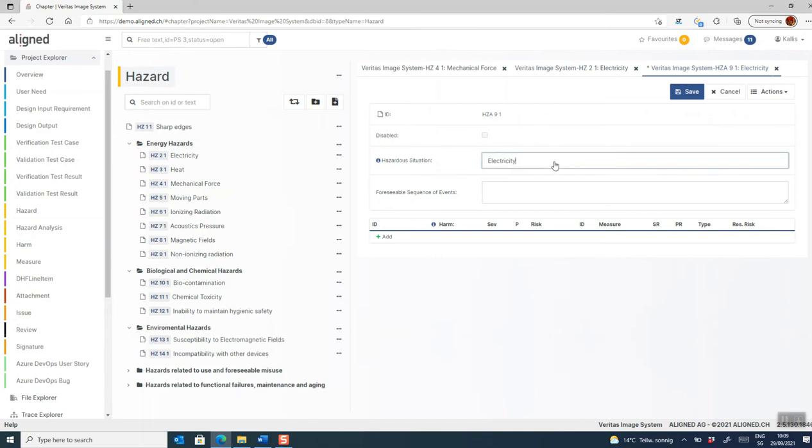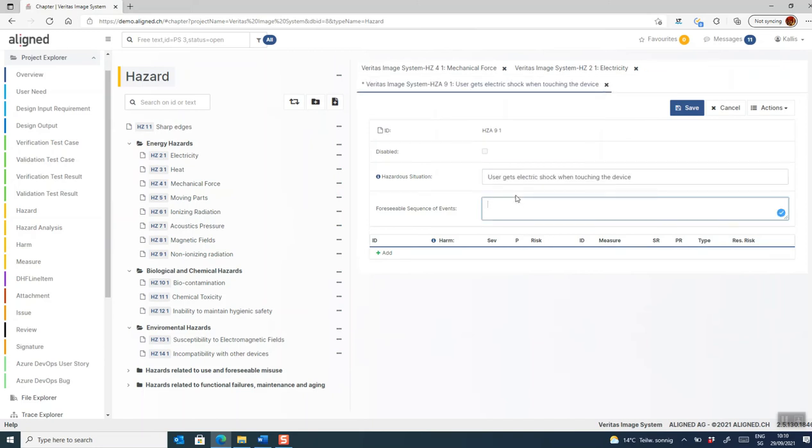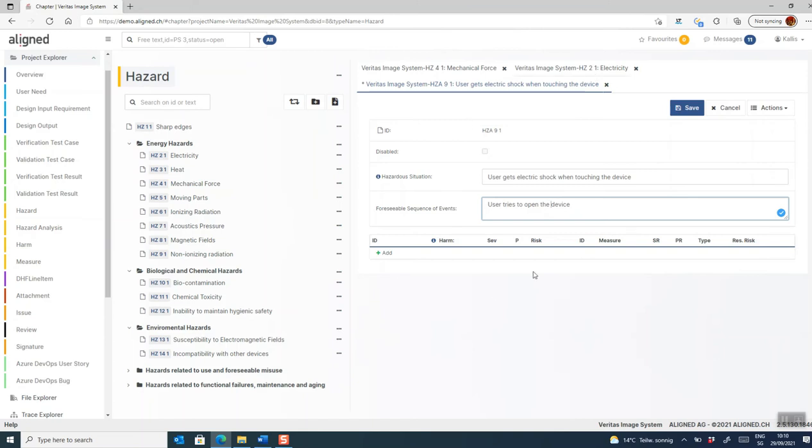So we can now add a hazard situation description and add a foreseeable sequence of event. In the next step, we will add one or more harms to this particular situation. So which harm do we foresee happening from the situation?